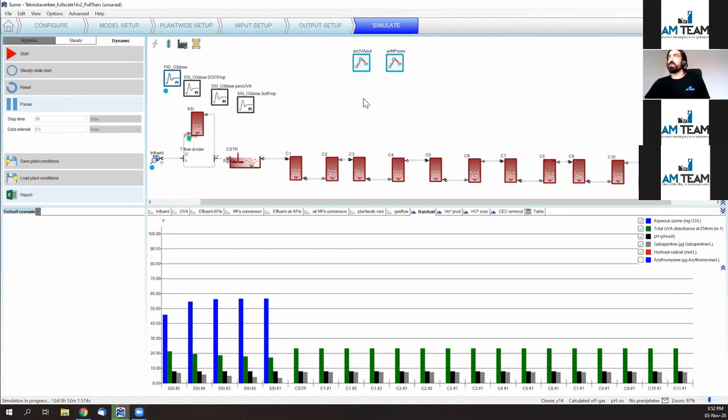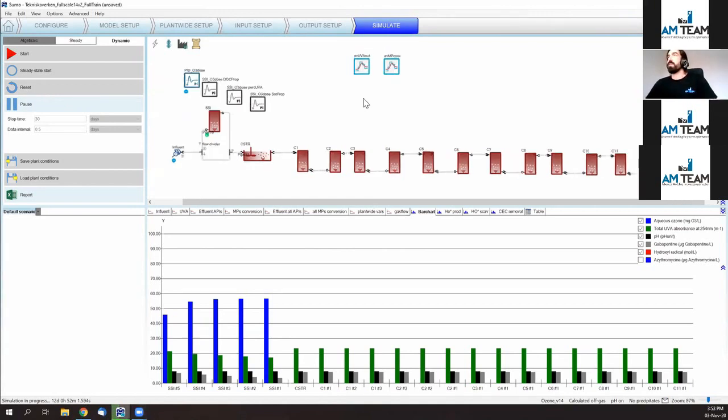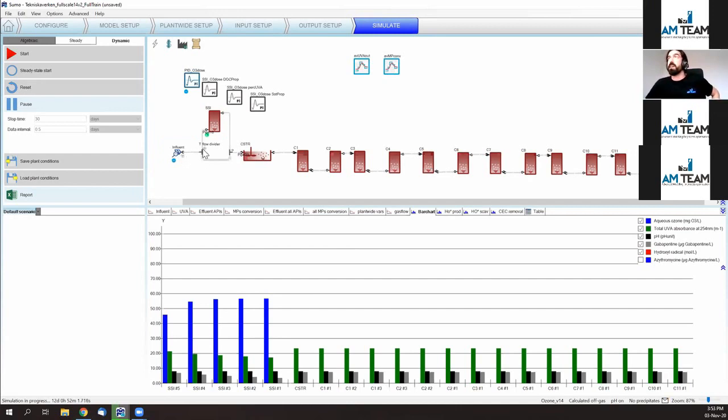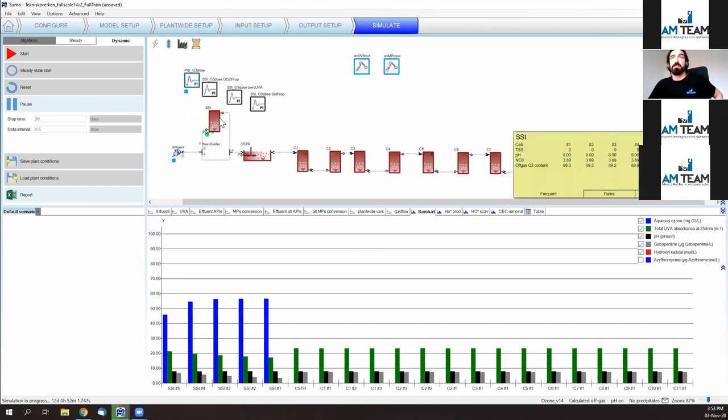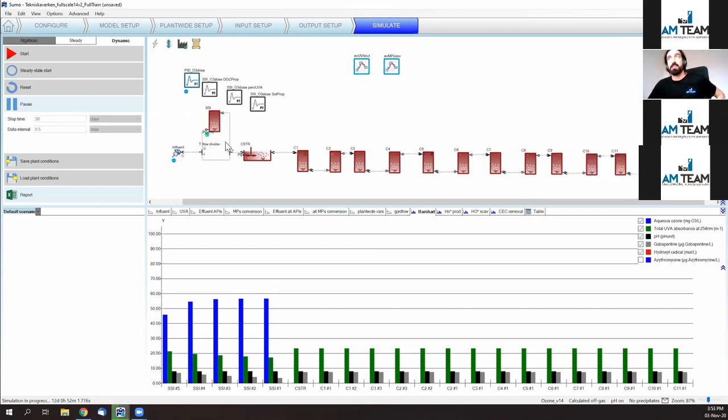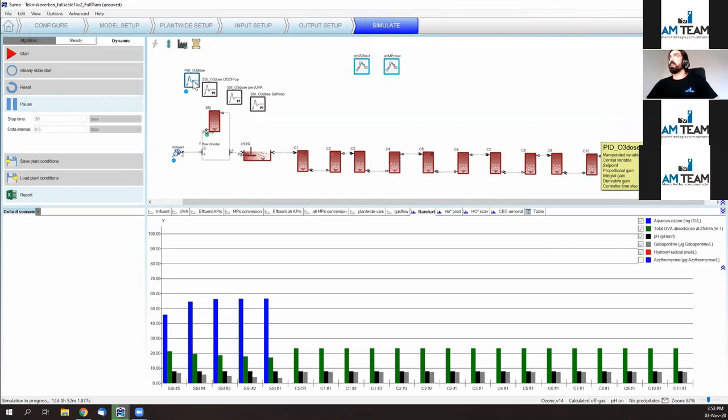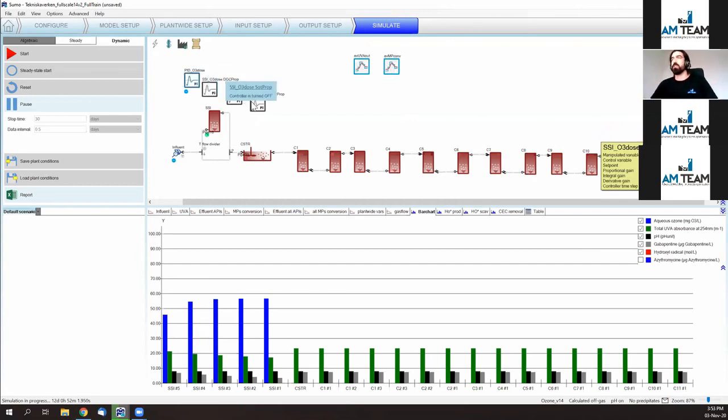All right. Let's go to the virtual representation of the full-scale plant of Linköping in Sweden. Here, as has been explained, comes the effluent of the upstream treatment plant. You have the split to the side stream injection where 10% of the incoming flow is directed. You inject the ozone, you join the mainstream again, and you let the reaction happen in the rest of the installation. As similarly to the previous demo, you can apply different control strategies. You can pick and try different controls without affecting the real plant.